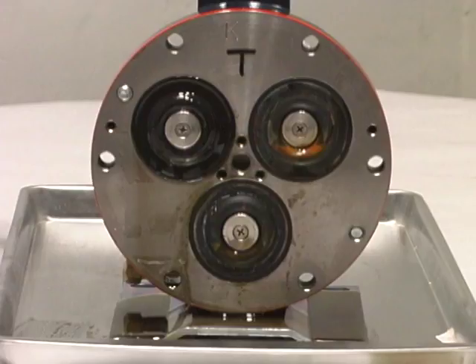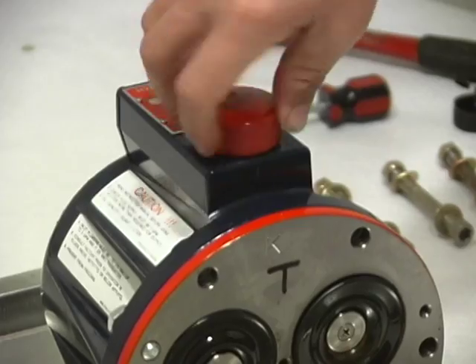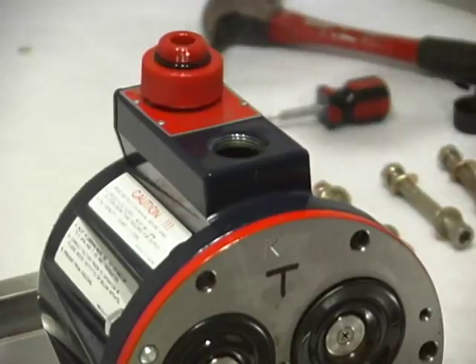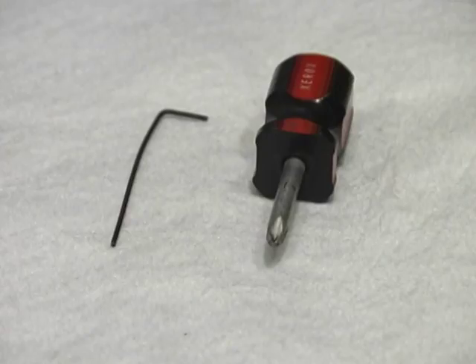If there is a break or cut in a diaphragm, replace it. Visually inspecting the oil reservoir is the only way to know if oil has been leaking. Remove the cap and visually check the oil level.